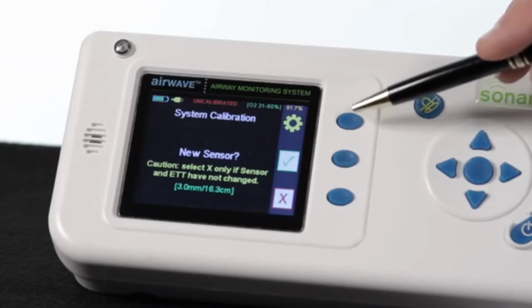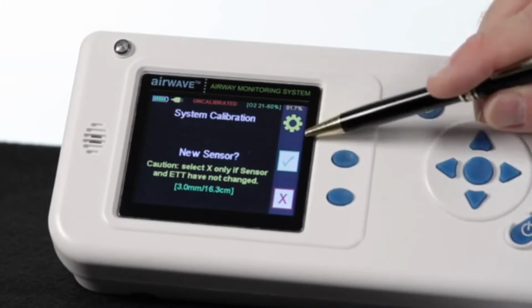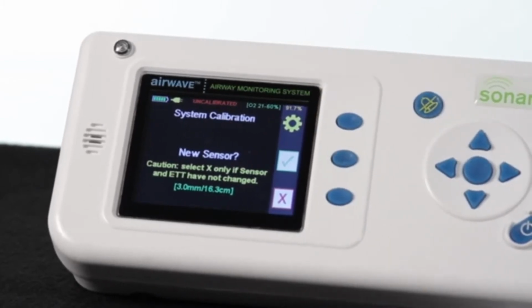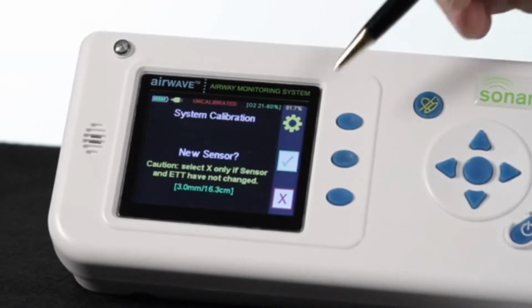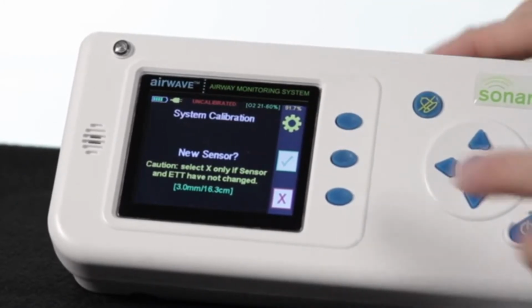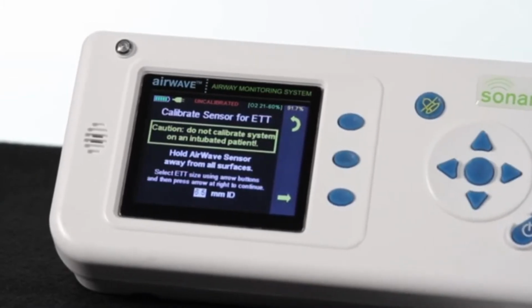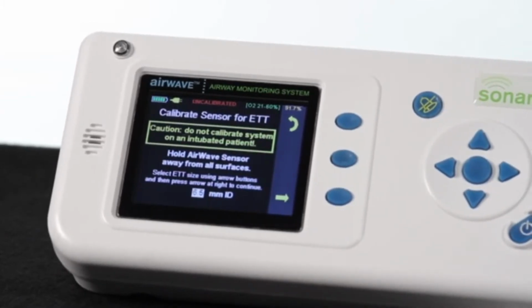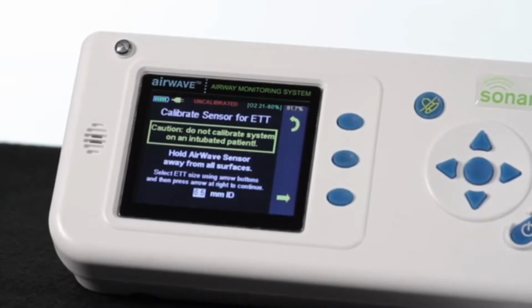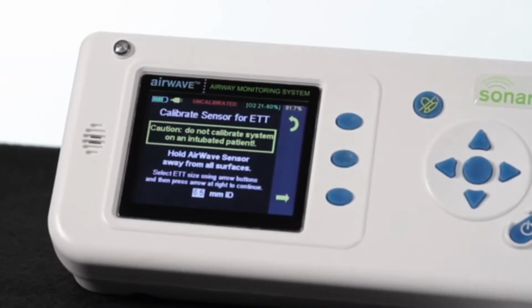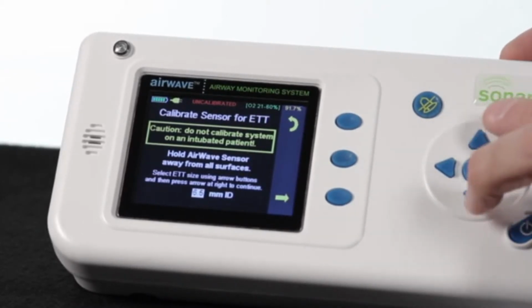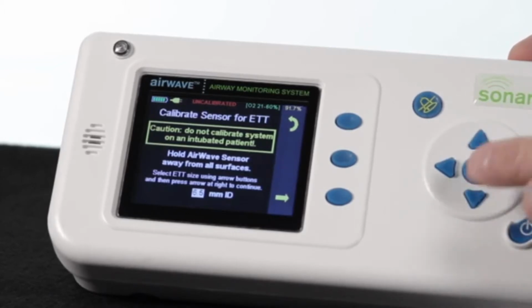And there's 3 blue buttons that correspond to the different actions to the left of them. Because we're using a new sensor, we want to check the green check, which would mean we would hit the button just to the right of that green check. Now the device is asking us for the size of the endotrach tube that we're using. It currently is set for a 6.5 millimeter tube, and we're going to be using a 3 millimeter tube on this baby. So we'll use the control buttons over here to the far right. These will increase and decrease. These will move the cursor left and right, and this is our enter key.